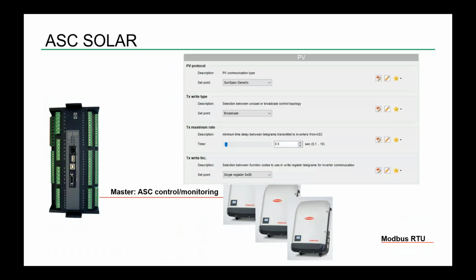So when you set up a Fronius system, it's a SunSpec implementation. What you do is select the SunSpec protocol, generic SunSpec. It's a broadcast type, so we send to all of the inverters at the same time. And SunSpec uses a single register implementation. You don't need to set that. So this is the setting that relates to the specific Fronius inverter.